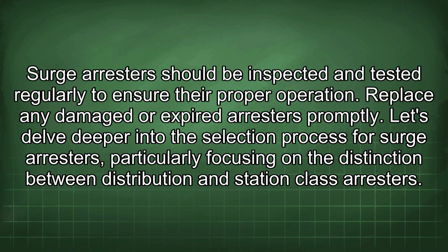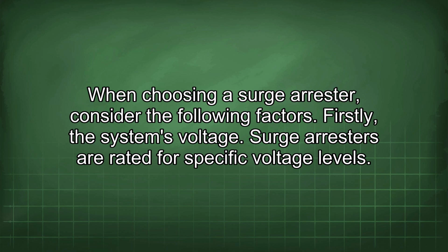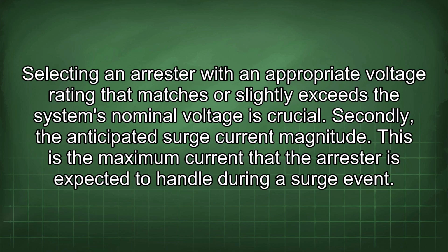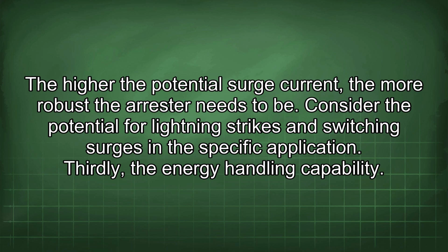Let's delve deeper into the selection process for surge arresters, particularly focusing on the distinction between distribution and station class arresters. When choosing a surge arrestor, consider the following factors. Firstly, the system's voltage. Surge arresters are rated for specific voltage levels. Selecting an arrestor with an appropriate voltage rating that matches or slightly exceeds the system's nominal voltage is crucial. Secondly, the anticipated surge current magnitude. This is the maximum current that the arrestor is expected to handle during a surge event. The higher the potential surge current, the more robust the arrestor needs to be. Consider the potential for lightning strikes and switching surges in the specific application.